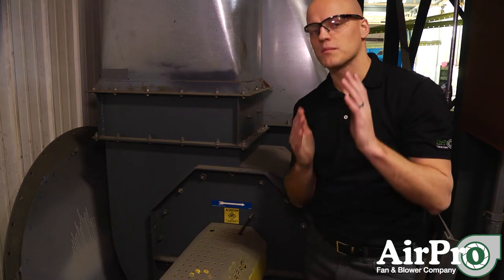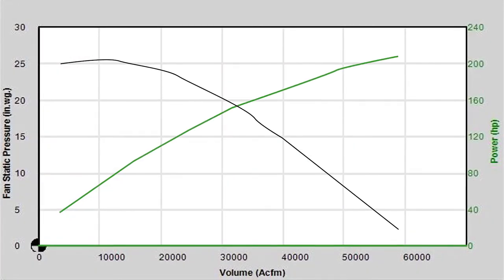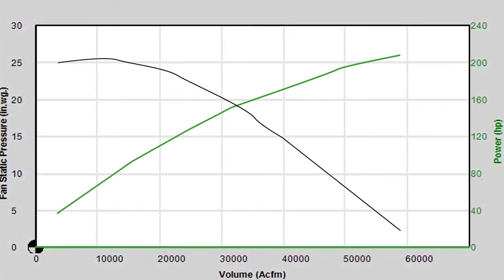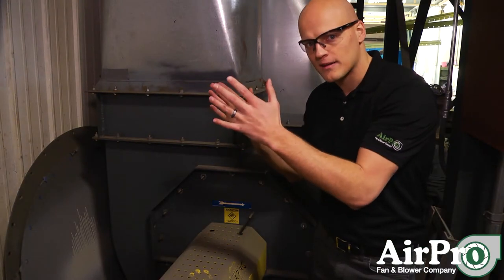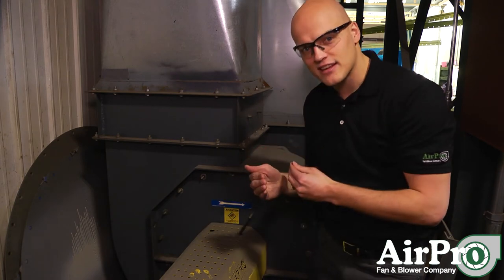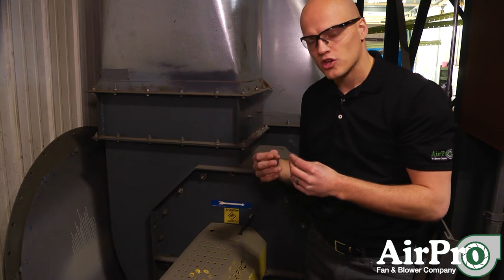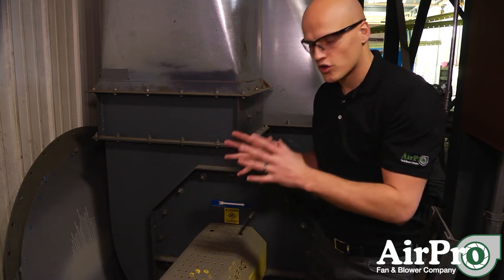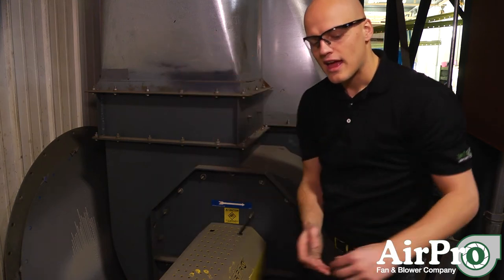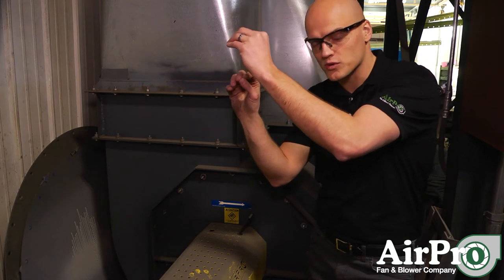If those line up, you can be confident that the volume going through your fan corresponds to where that static pressure point was on the static pressure curve. Now all of that has to apply to your actual scenario. In an ideal situation, the curve you're looking at must be accurate in terms of the speed the fan is running at and the density of the gas moving through it. If you have the speed wrong or the density of the gas wrong, your curve won't show you exactly what you're doing. Your curve has to be based on those two parameters, and then your differential static pressure and amp draw should line up very close to what you see on the curve.